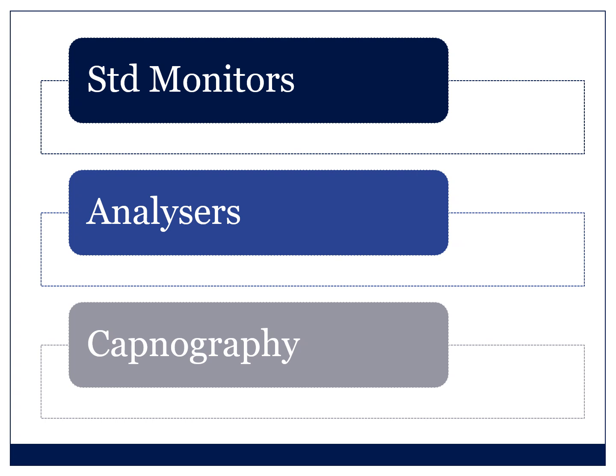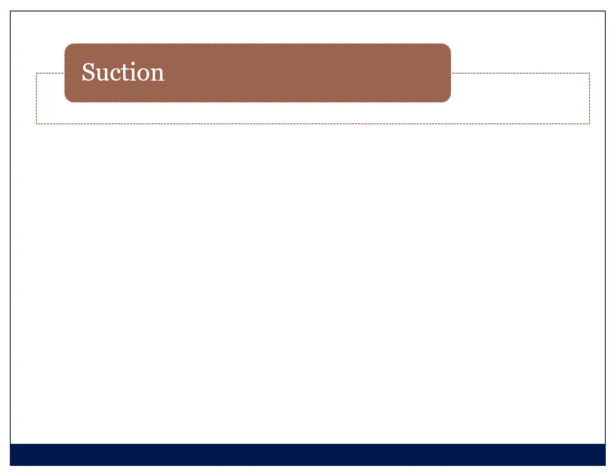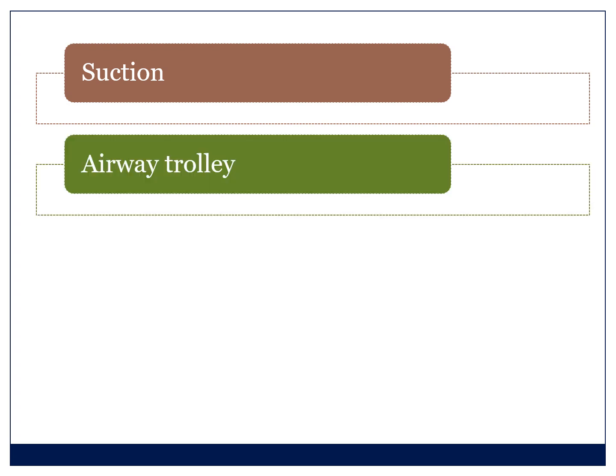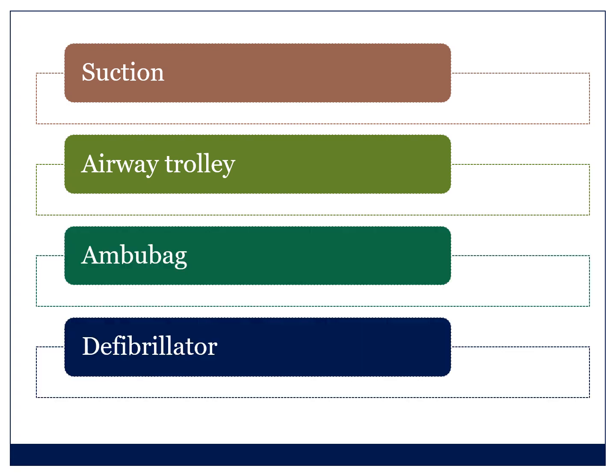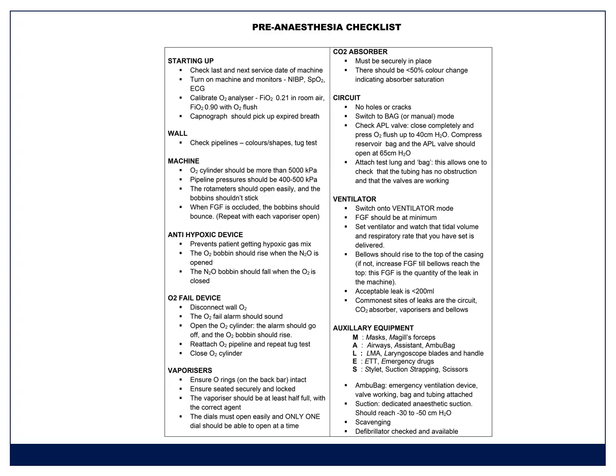It's a little bit alarming to find that your capnography is not working once the patient's asleep. So the other check for this is that when you've got the mask on the patient and you're pre-oxygenating, make sure you're getting your CO2 trace, because it's a difficult thing to fix once you've started. And then those other things we talked about, check that your suction's working, check your airway trolley, it's part of the anesthetic machine check, make sure you've got a working ambu bag, and make sure there's a defibrillator somewhere in theatre that's charged and ready to go. And that's all part of the equipment check in the perioperative phase.